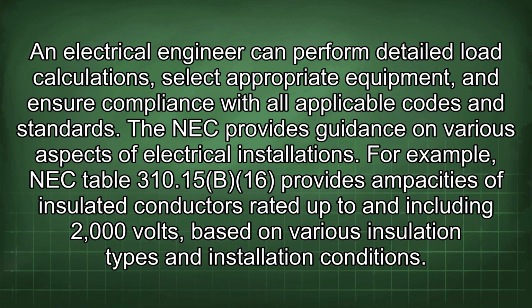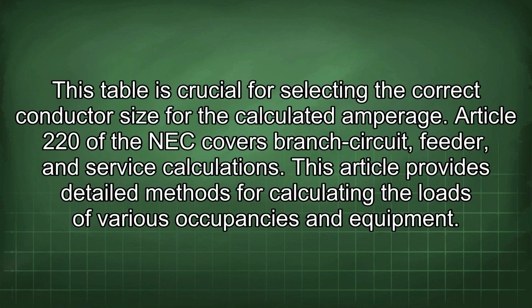The NEC provides guidance on various aspects of electrical installations. For example, NEC Table 310.15(B)(16) provides ampacities of insulated conductors rated up to and including 2000 volts based on various insulation types and installation conditions. This table is crucial for selecting the correct conductor size for the calculated amperage.